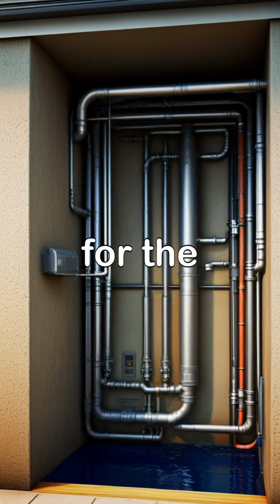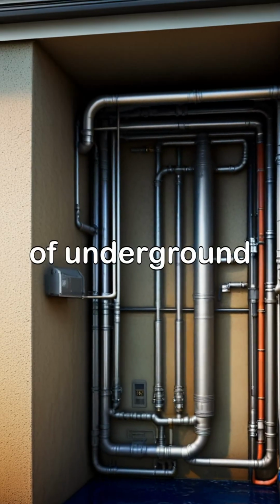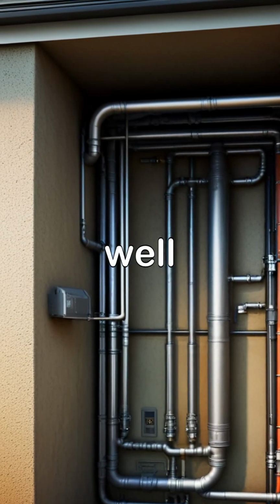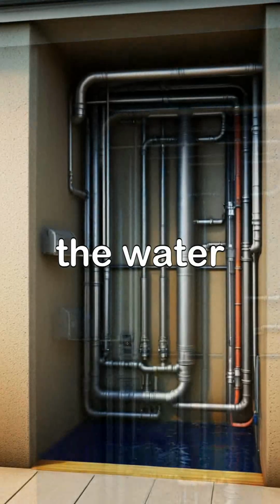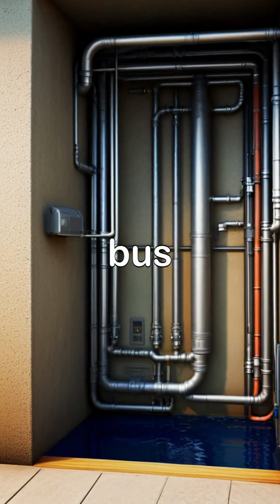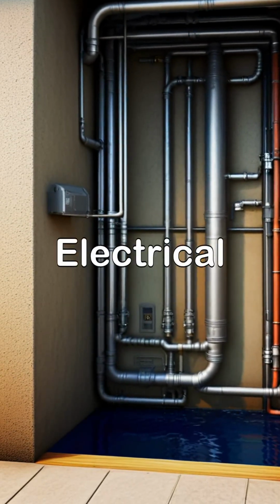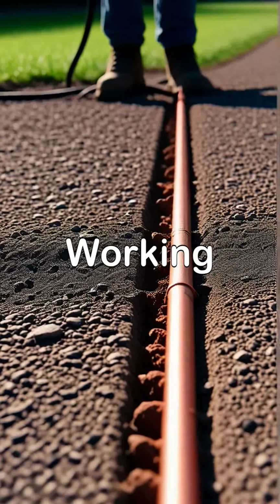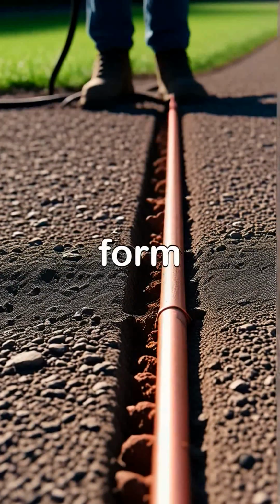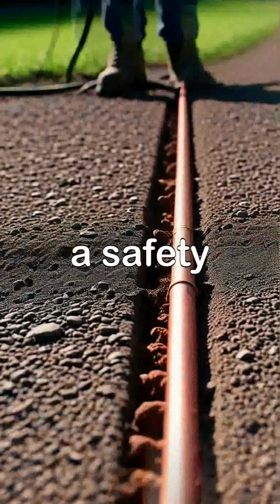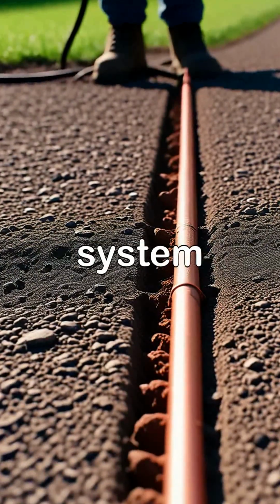If the water system for the home includes more than 10 feet of underground metal water pipe, including metal well casing bonded to the pipe, the water system also is connected to the neutral bus bar, as specified by the National Electrical Code, NEC. Working together, the ground rod and the water pipe form the grounding electrode system that provides a safety path to earth for the electrical system of the home.